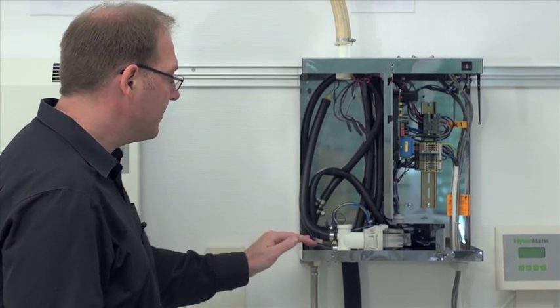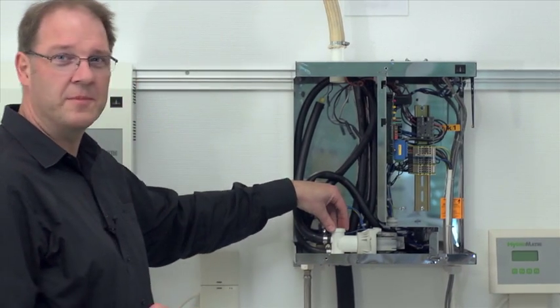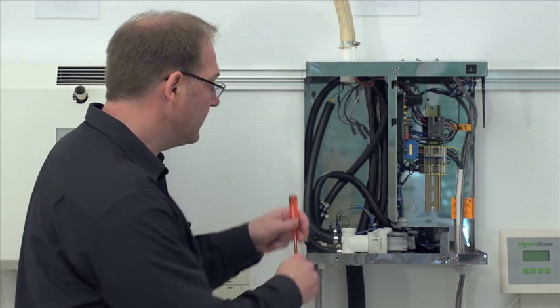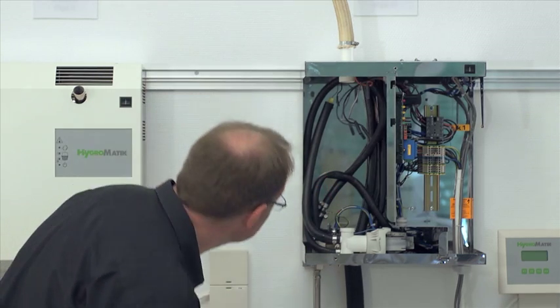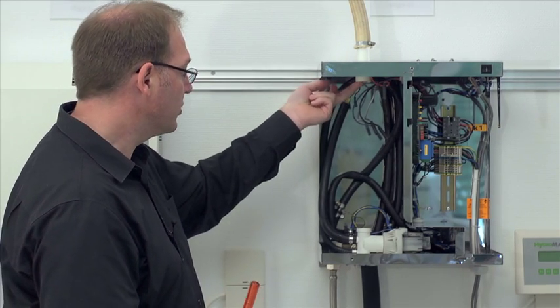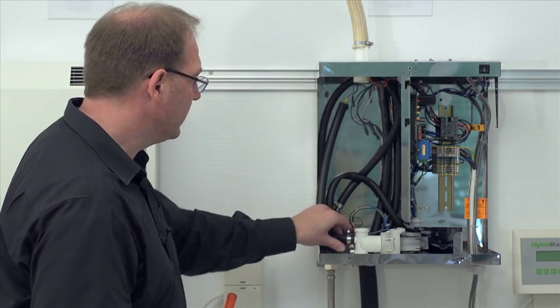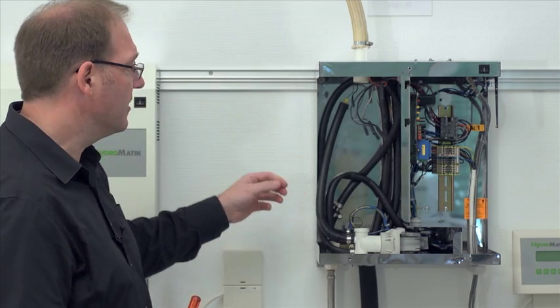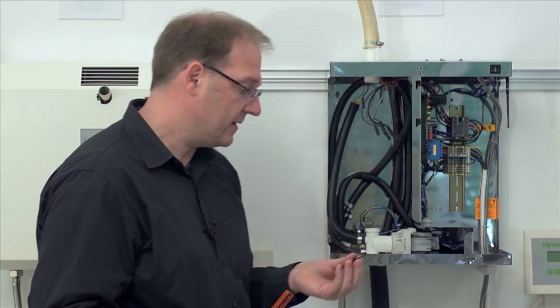Before I place the steam cylinder back into the unit, I check the base for any lime scale deposits. I remove the deposits. I especially check this area where the o-ring is later seated. Same applies to the steam hose adapter on top, it must be clean and free of mineral deposits. And besides that, I can check if all the hoses are positioned properly, are tightly sealed, and then I take another look at all the cables to see if any of them are cracked or otherwise flawed, none are squashed.